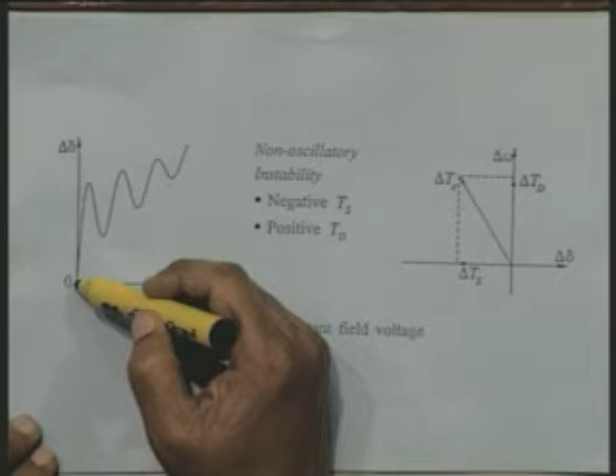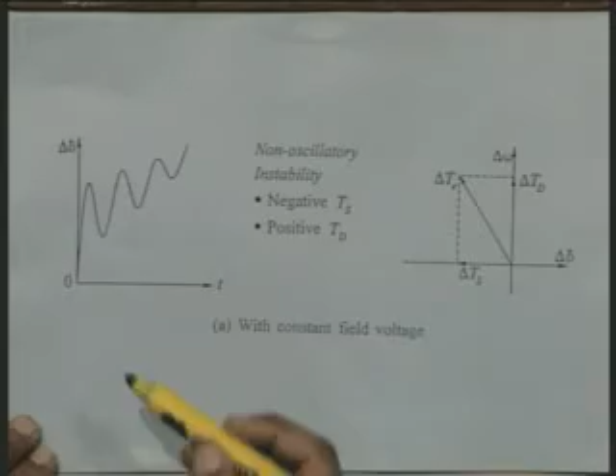Now suppose the situation is like this, where you have a negative synchronizing torque while positive damping torque. The response of the rotor to small perturbation will be of this form, starts from 0, and these oscillations are damped, because damping is positive, but since synchronizing torque coefficient is negative, it increases monotonically. Therefore, this represents a case of insufficient synchronizing torque.